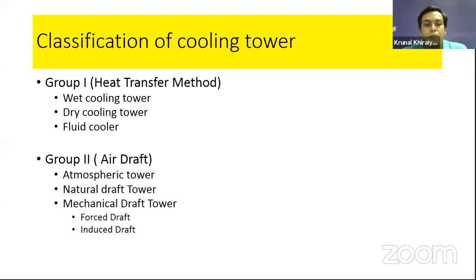Mechanical draft is further classified into two groups: forced draft and induced draft. In forced draft, the air moves from bottom to top, and in induced draft, it also moves from bottom to top, but the position of the fan is different. In forced draft, the fan is located at the bottom of the tower, near the louvers, and in induced draft, the fan is located at the top of the column.